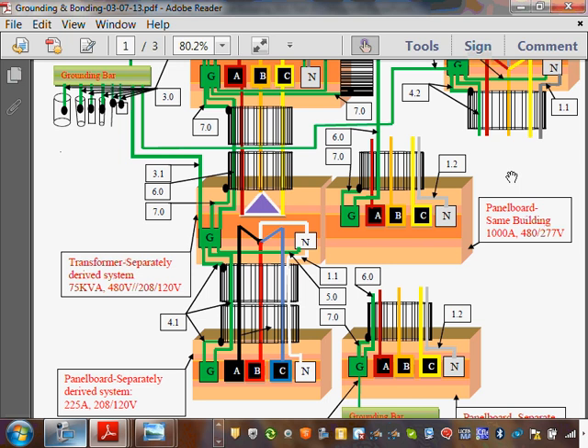Completely separated between. The only thing that ties the whole system together is what? The grounding and bonding. You still have to ground and bond ahead of the separately derived system and after the separately derived system. Okay, so my delta-Y is typical. I brought my feeders here. The first thing you need to do when you have a separately derived system, as the code says, is take a grounding electrode conductor either to the transformer, which you want to operate, or to the panel, typically at the transformer level, and that conductor right here, 3.1, take it all the way to the grounding electrode system inside your building. Tie it to your grounding electrode system inside your building.